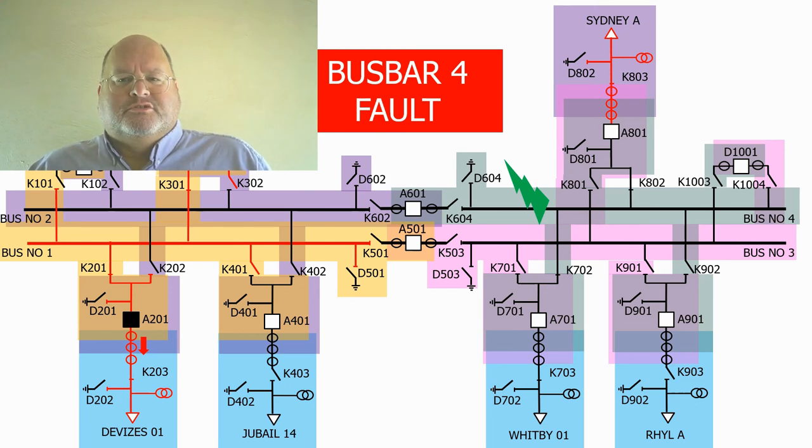The busbar zones for each circuit are switched using the isolator contacts, ensuring of course that no current transformers are ever open circuited.